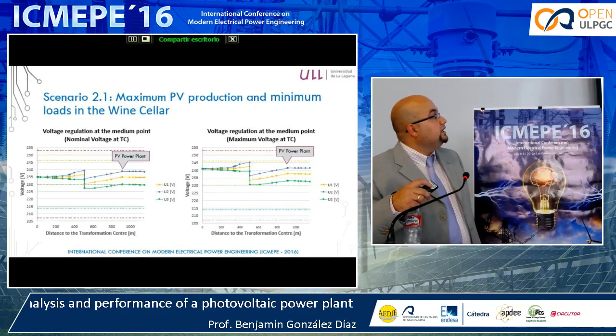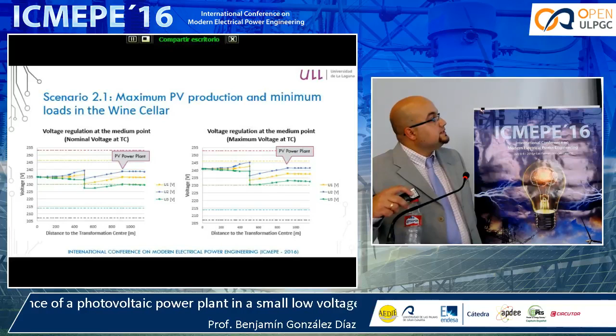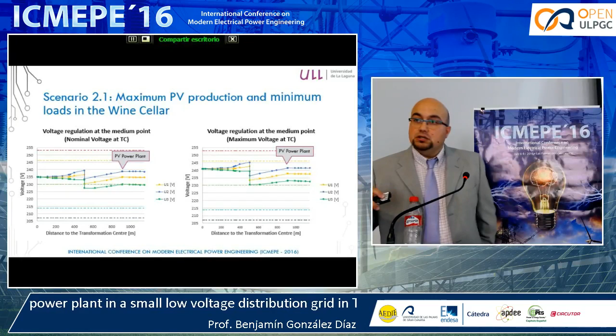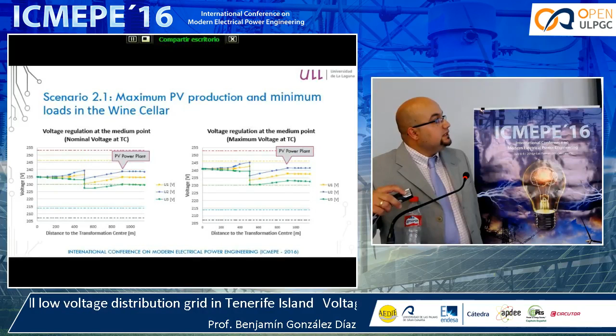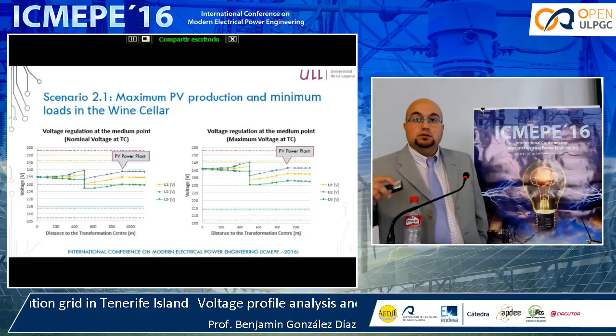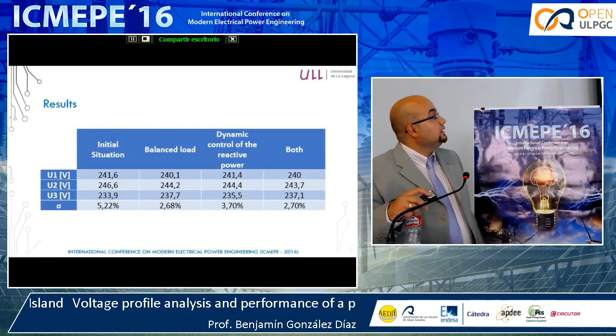What about putting this line voltage regulator in the middle of the line? So we have it here in the middle, and they are exactly where they must be, but if the maximum voltage is needed at the transformation center, one of the points is near reaching the limit. So perhaps it would be more interesting not to put it exactly at the wine cellar, but exactly in the middle of the line. With these strategies, we are passing from around 5% to about 2.7% variation of the voltage through the lines.